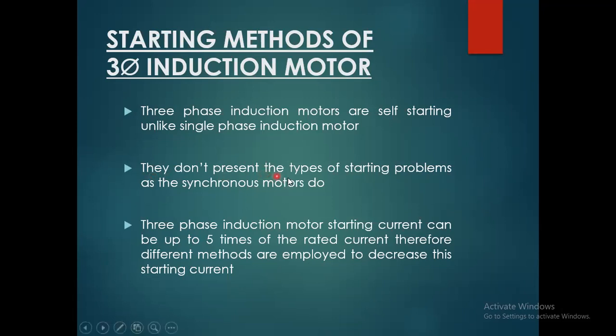They don't present the types of starting problems as synchronous motors do. The starting current of a three-phase induction motor can be up to 5 times the rated current. Remember this. Why? Because we need to connect a starting mechanism and select the breaker to provide supply to the three-phase induction motor. Remember, it's 5 times the starting current at the initial starting of the induction motor.